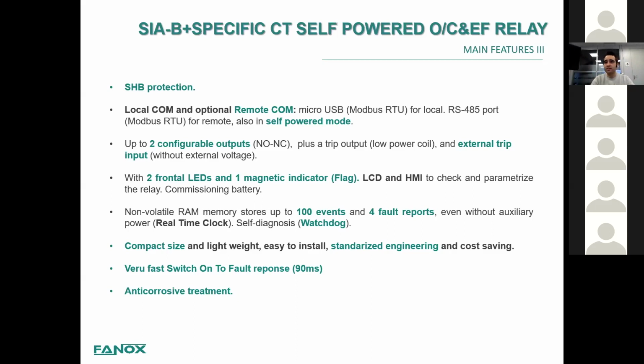Of course, an LCD and HMI to check and parameterize the relay with a commissioning battery. So you can go to a completely unpowered substation and just with the commissioning battery, check if the relay is working and check the settings, configuration, and so on. Regarding storage of the events and faults, we can store up to 100 events and 4 fault reports.